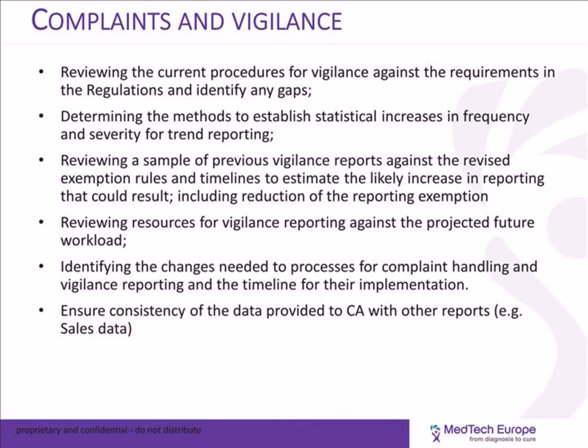There's this interesting request for trending, which applies to the non-reportable event in the Medical Device Regulation. And the only requirement is that a significant increase triggers reporting. So significant increase will have to be defined in terms of frequency and severity. And this is not described in the regulation and is to be defined internally by each manufacturer, depending on the risk class of their device.